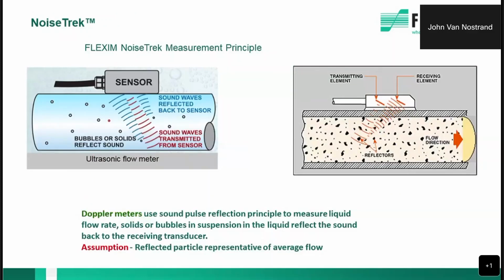So we also offer a feature called NoiseTrek, and NoiseTrek is a Doppler technique that works by sending a beam of energy that's tuned to a precise frequency through the wall of the pipe, and it's looking for something to bounce off of, a particle in the water, for example. It works well if there's aeration or bubbles in the water. Normally, we don't use the NoiseTrek feature. In water applications, we very seldom need it.